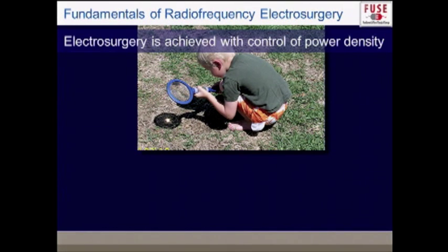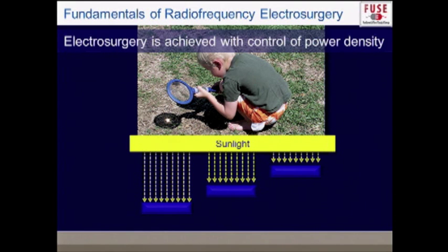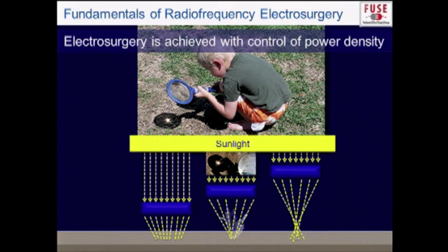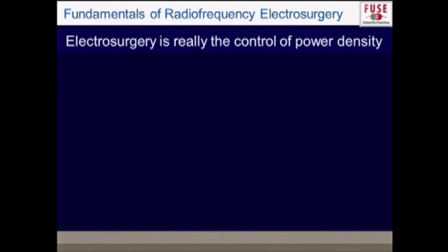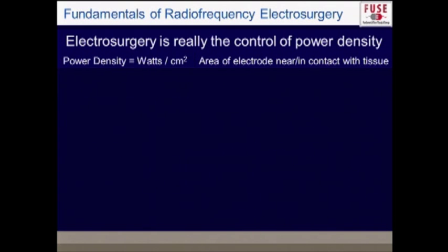At a surgical level, what you're really controlling is power density — it isn't about what label is on the output, it's about power density or current density, measured in watts per centimeter squared. Think of a magnifying glass focusing sunlight: when the focal point is right, you elevate the temperature of what you're focused on. It's the area of the electrode that is near to or in contact with tissue that determines current density.